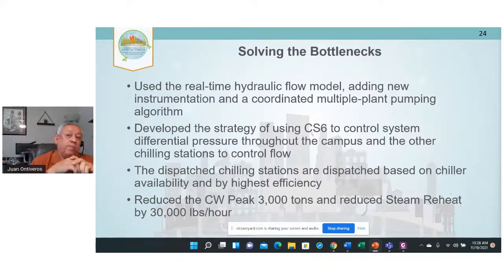And so basically the way our system works is it tells our operators to start a chiller or stop a chiller as the load grows. They then dispatch it based on which chiller is available, making sure that it's available, and which one is the highest efficiency. So it's dispatched. Once they start it, our control system then starts to control the speed. And I'll go into a little bit here in a minute and show you how that works.